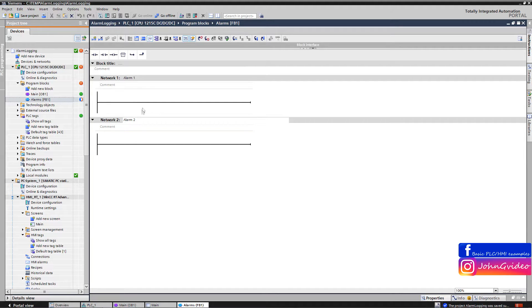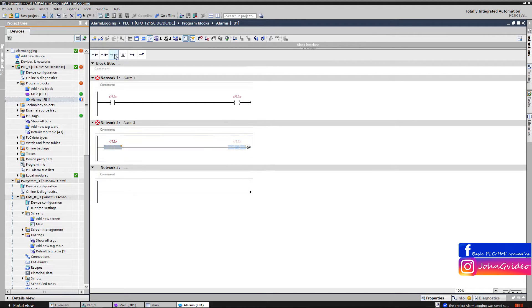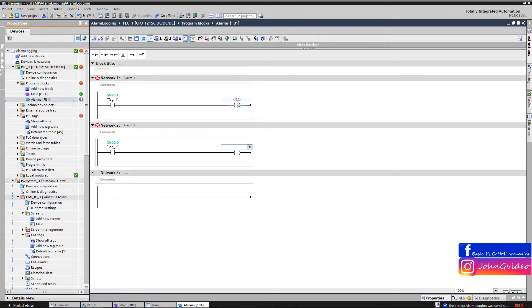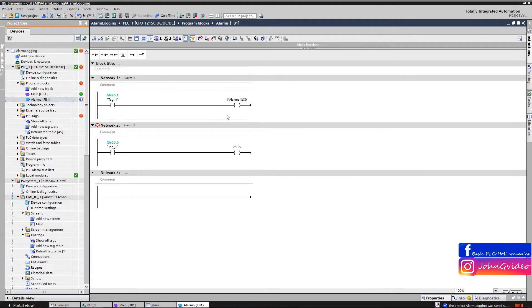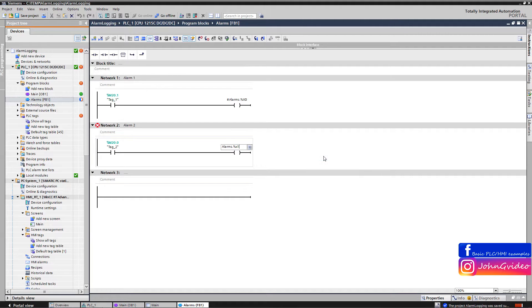For activating we use two markers. The first marker will be M20.1 and the second will be M20.0. If we set the first marker, we activate — respectively set — the first bit of the alarms Word. And if we activate the marker M20.0, we activate the second bit in the alarms Word.